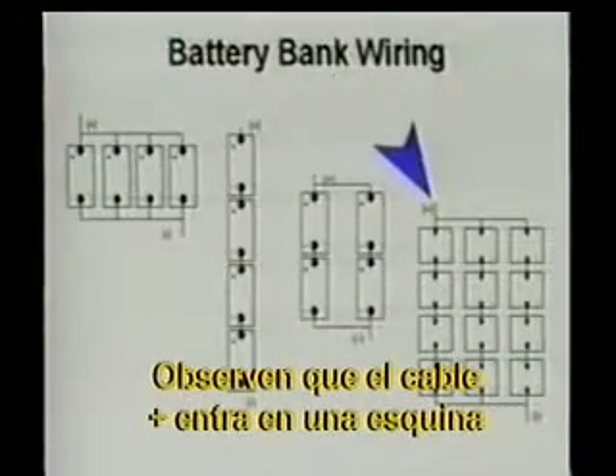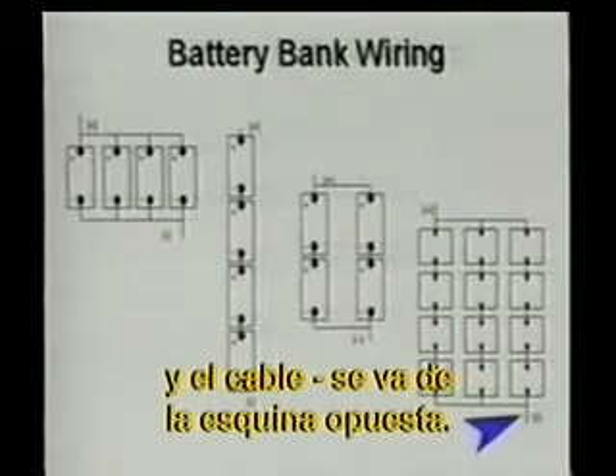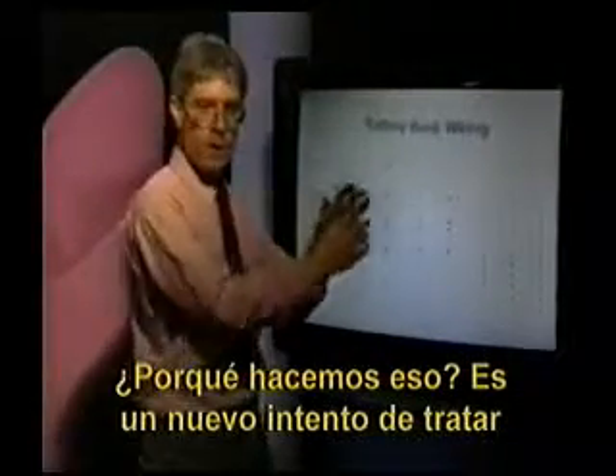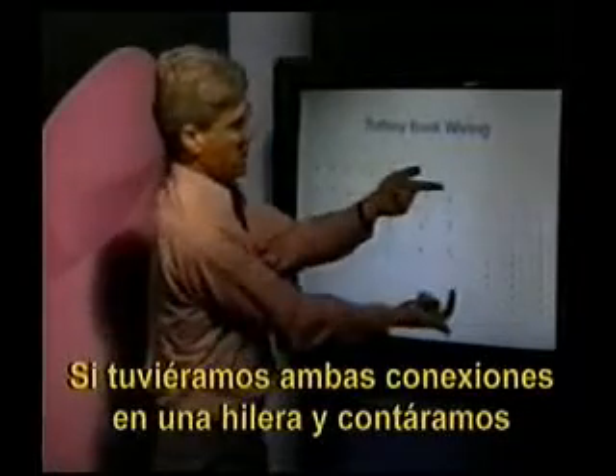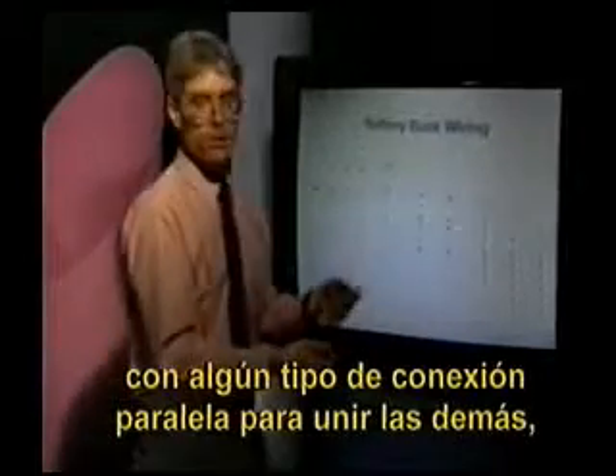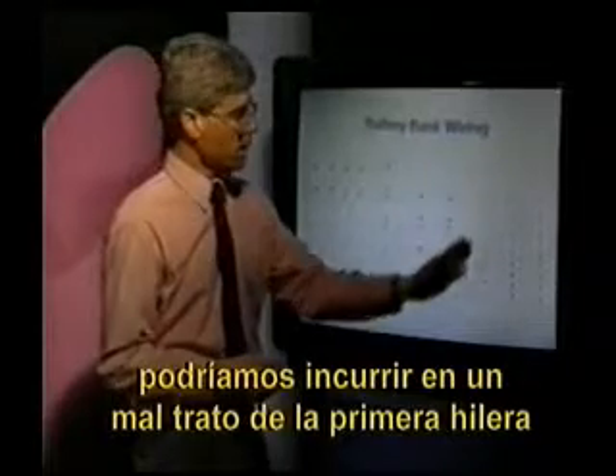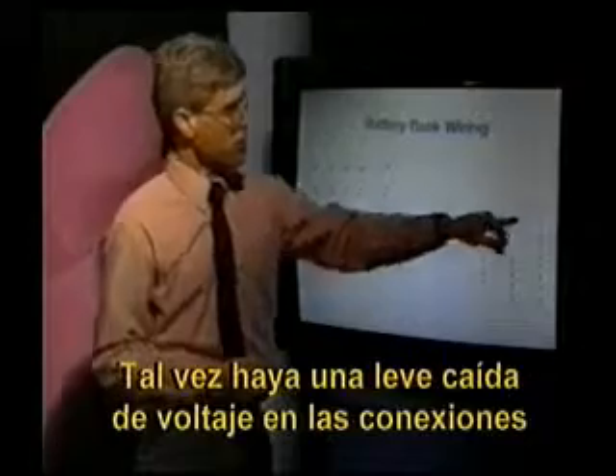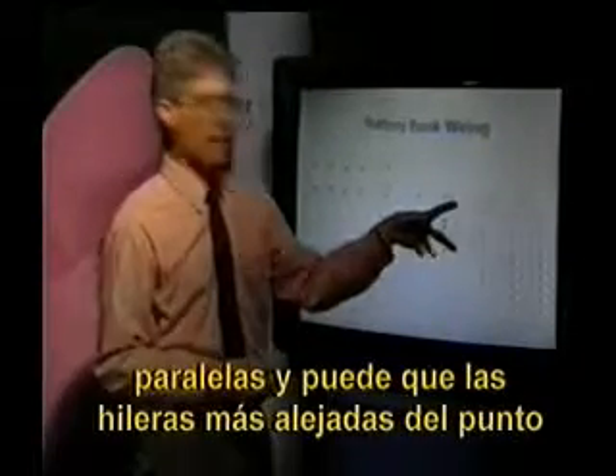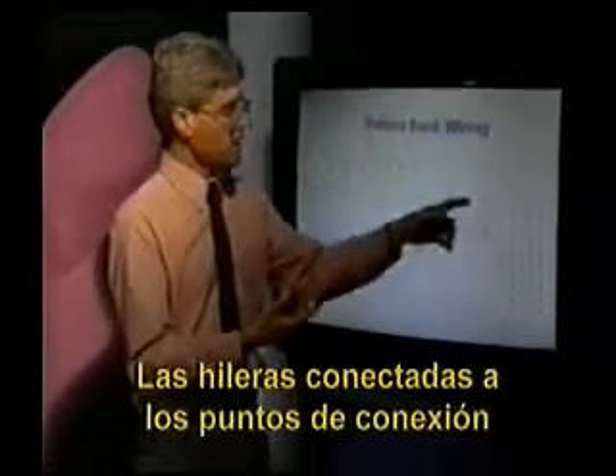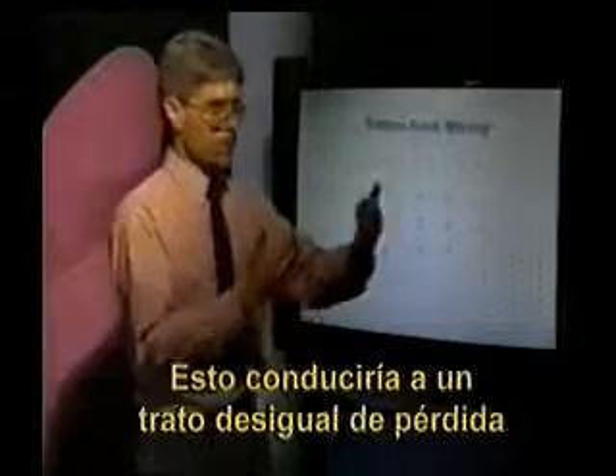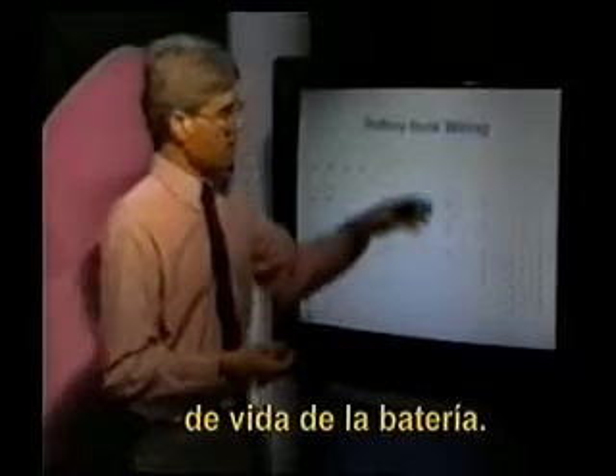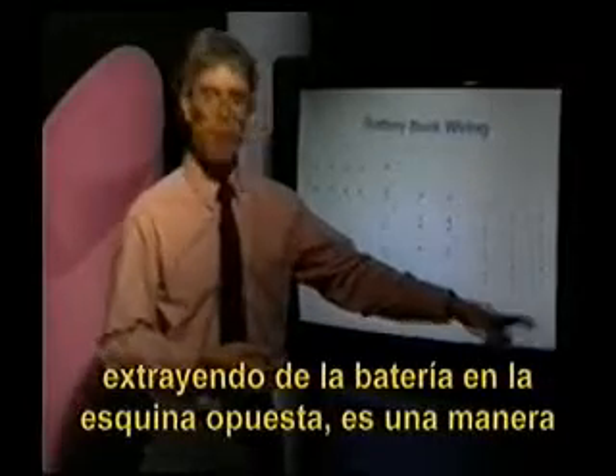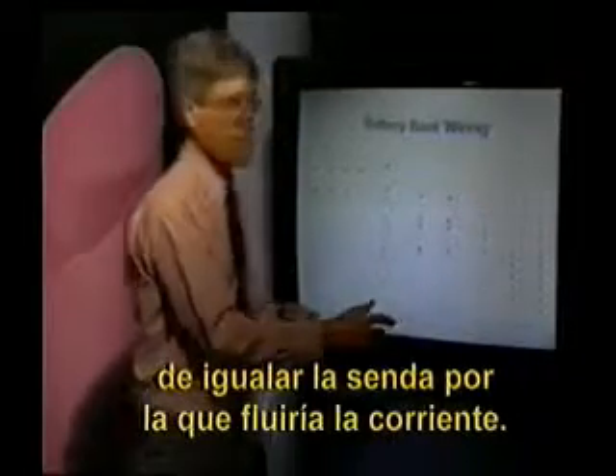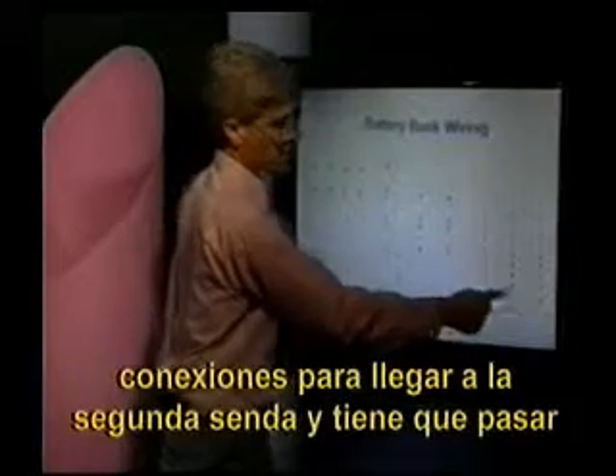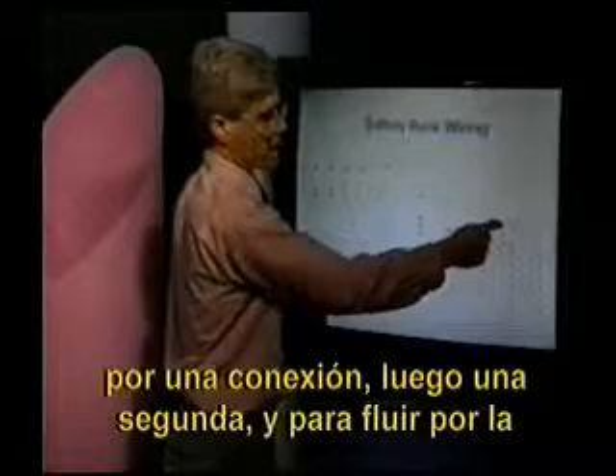Notice that the plus wire is coming in one corner and the minus wire is leaving from the opposite corner. Why are we doing that? That's a simple approach to trying again to equally treat all of our batteries. If we had both of our connections on one string and relied on some sort of parallel connection to link the other strings, we could possibly have a mistreatment of the first connected string compared to the later string. Perhaps there's slight voltage drops in the parallel connection, and the farthest strings away from the initial connecting point might not be charged as much. The strings connected to the connecting points might be charged too much. This would lead to an unequal treating of the battery and loss of life. So by simply bringing in one wire in one corner and tapping out of the battery bank at the opposite corner, I think that's one way to sort of equalize the path that the current would flow through. You can see that if current comes in and flows through the first path, it has to make a couple of connections. To get to the second path, it has to go through one connection and a second connection.